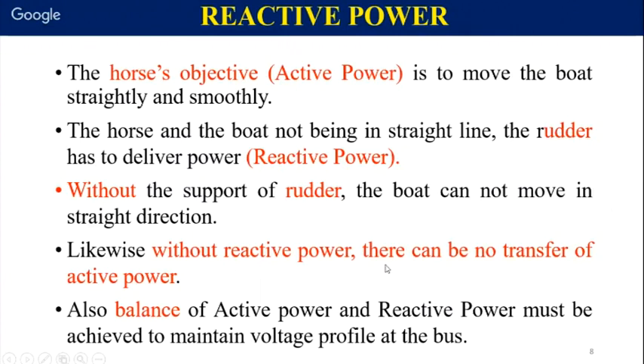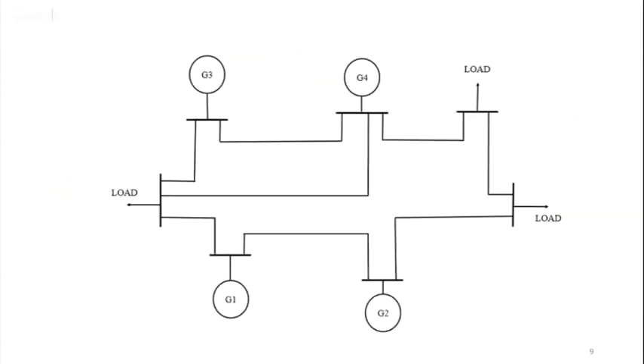You know, reactive power flows from higher magnitude to lower magnitude, whereas active power flows from leading angle to lagging angle. So reactive power is a part and parcel of transmission, you cannot avoid it, but it produces losses. But it is compulsory, it is a must, it should be in balance, and without it you cannot transmit active power. Now I will be showing with the diagram how reactive power affects, and if it is required in excess, that is, if it is not balanced, it will lead to voltage instability, which may even lead to blackouts.